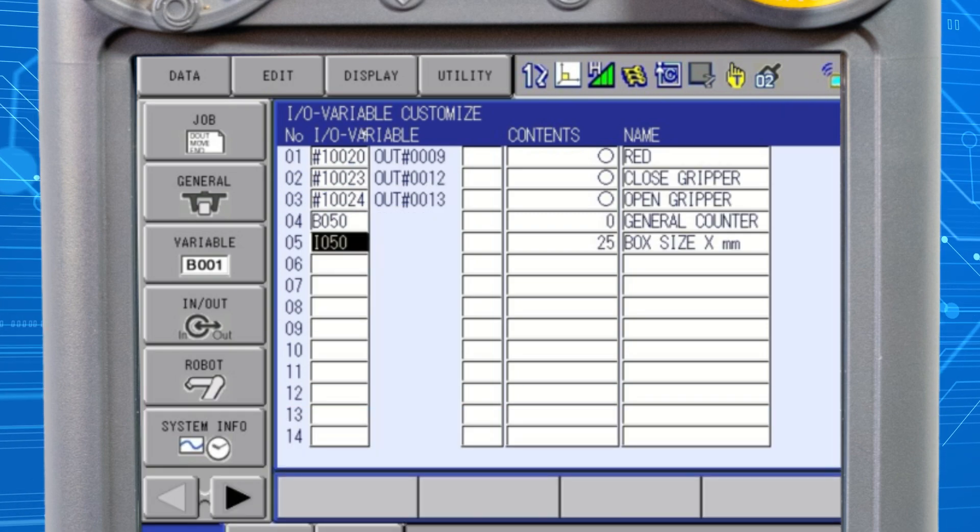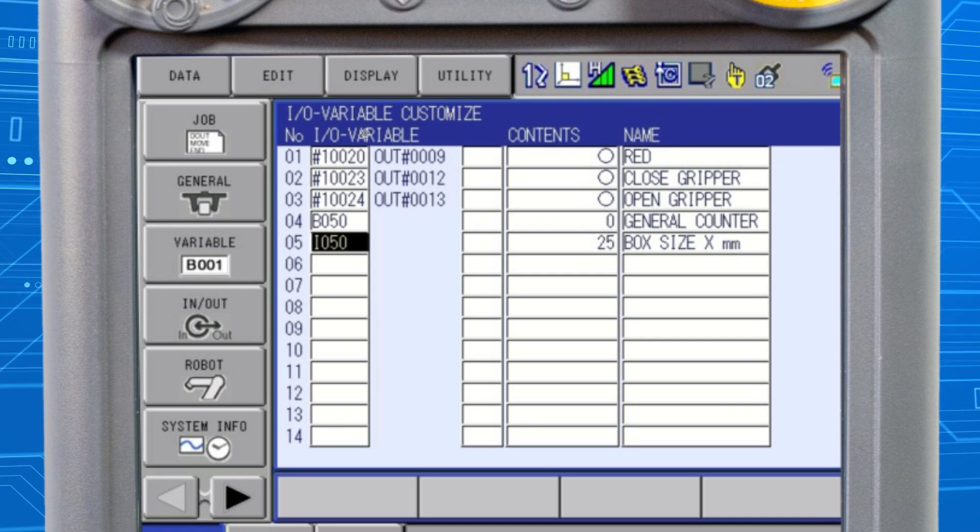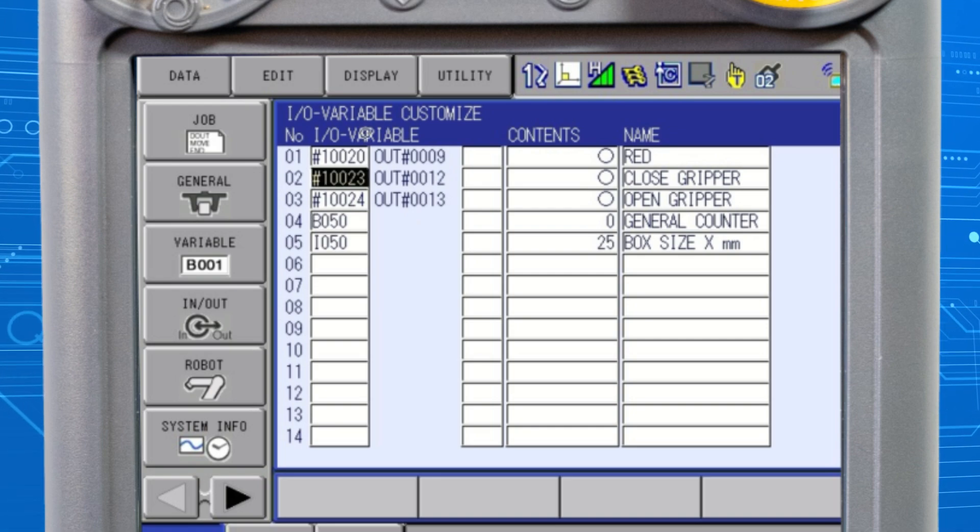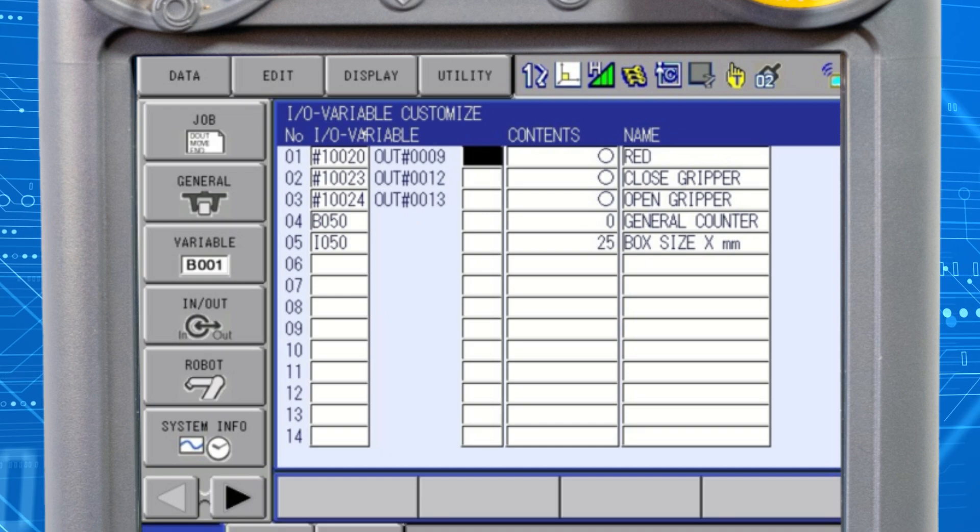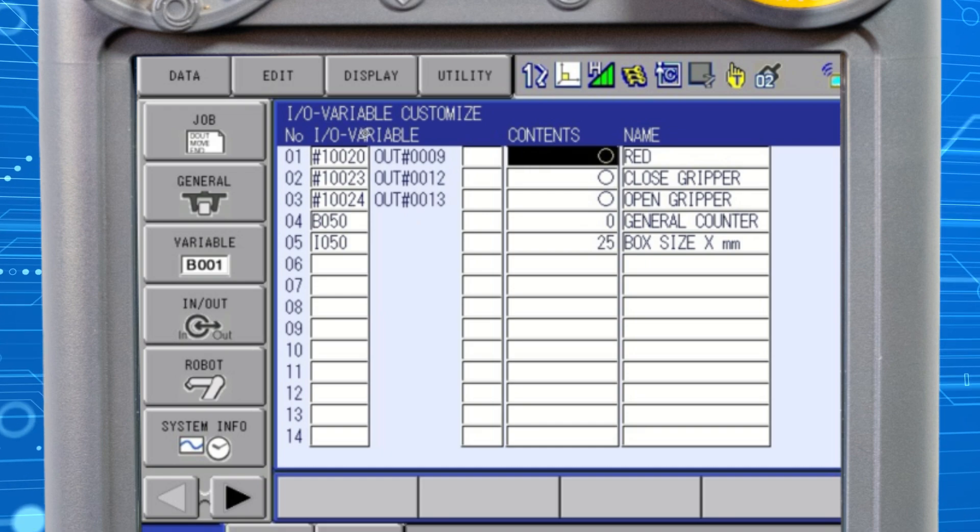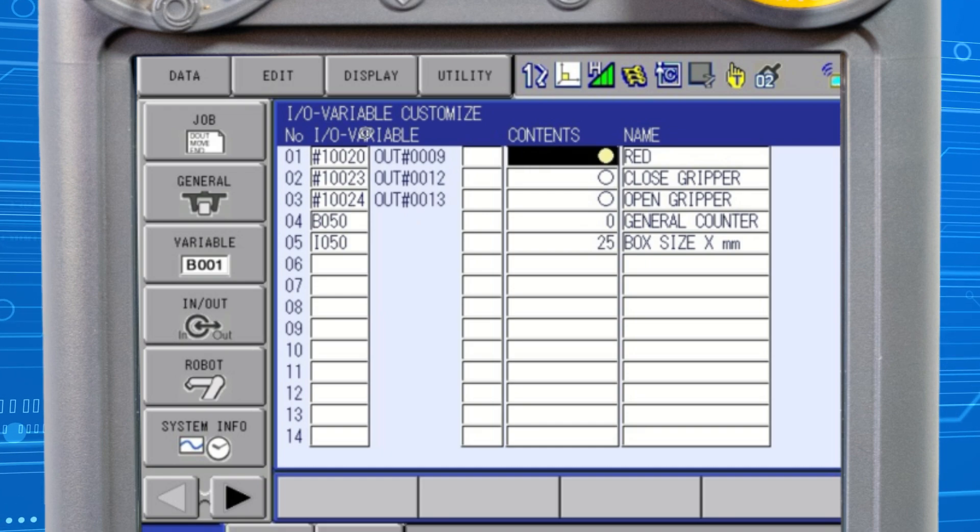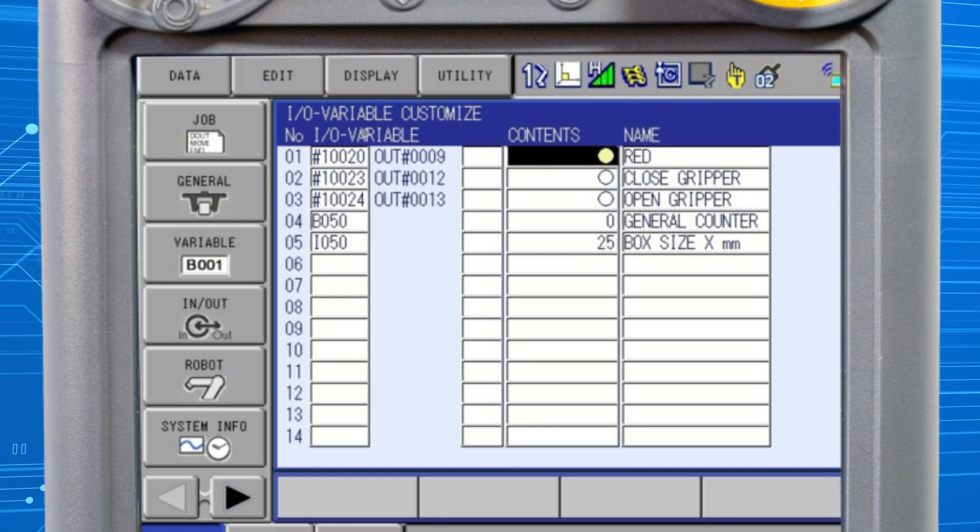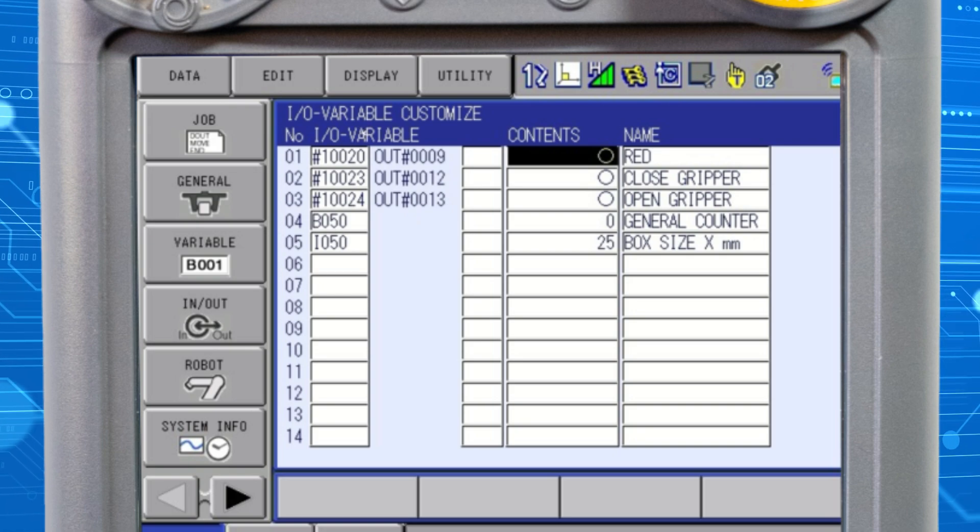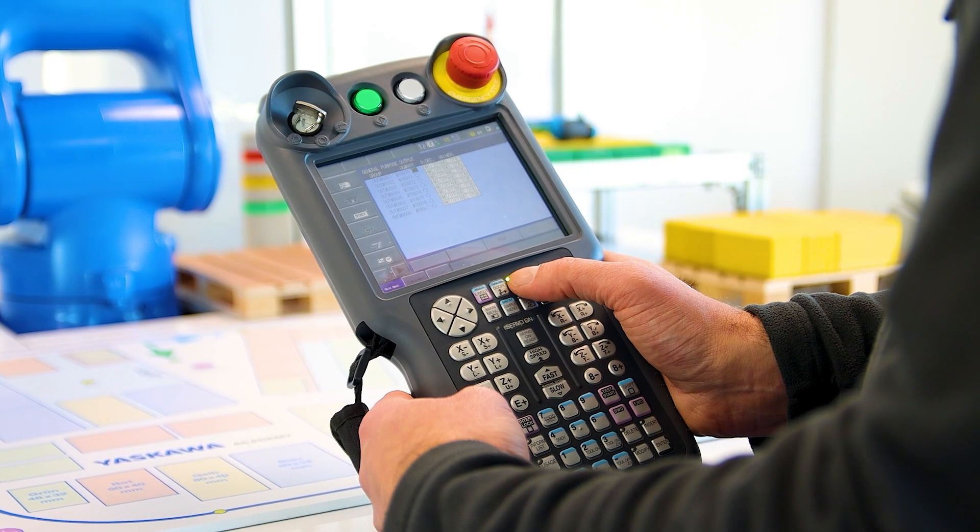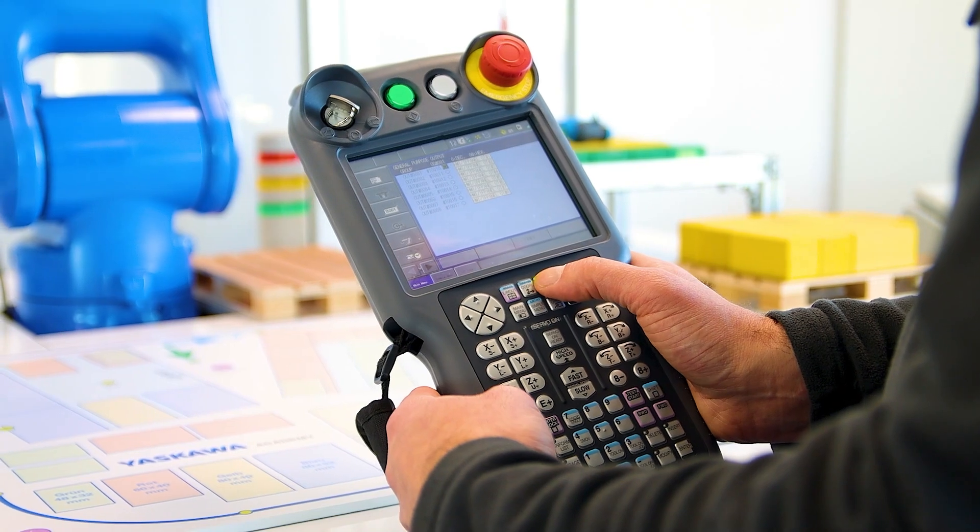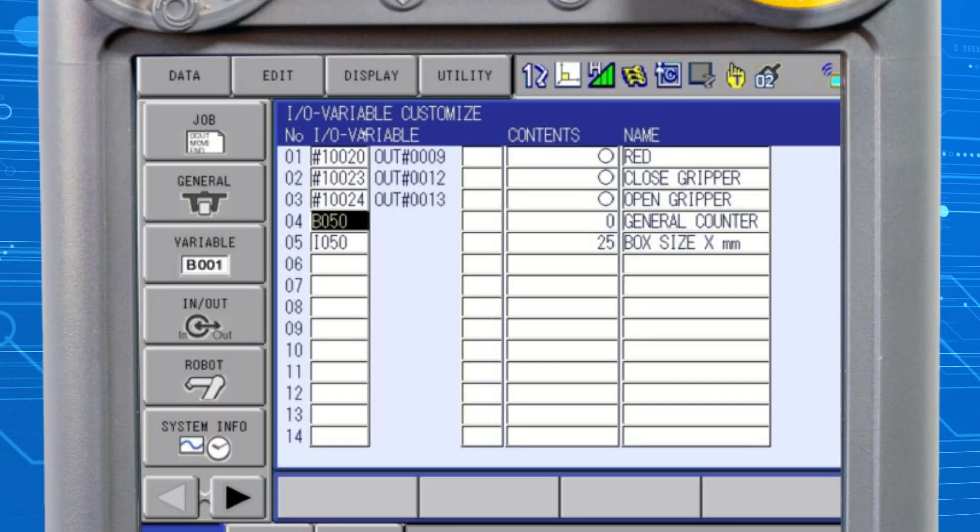To manually change the signal status from on to off or vice versa, place the cursor on the circle on the same line as the signal. If the circle is empty, the signal is in the off status. If the circle is filled, the signal is in the on status. With the circle highlighted, switch the signal status by pressing and holding the interlock button and then pressing the select button.